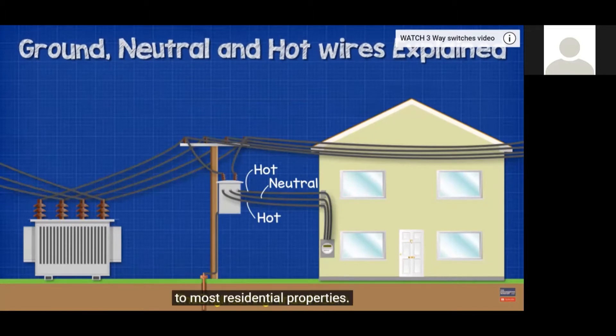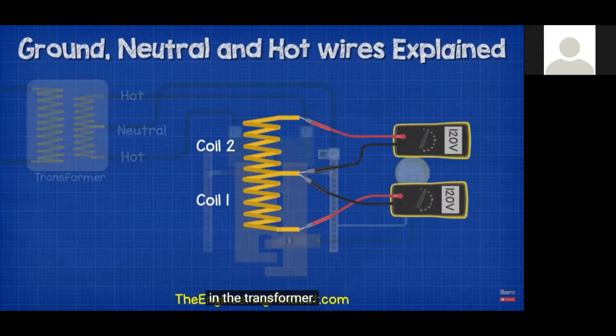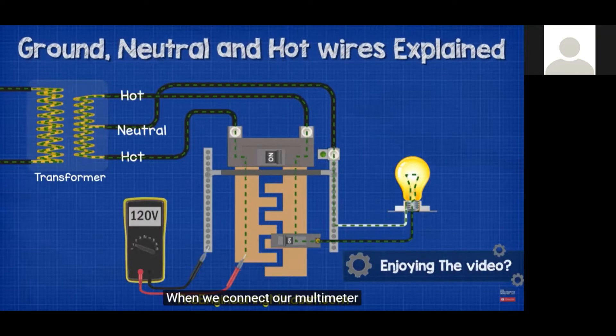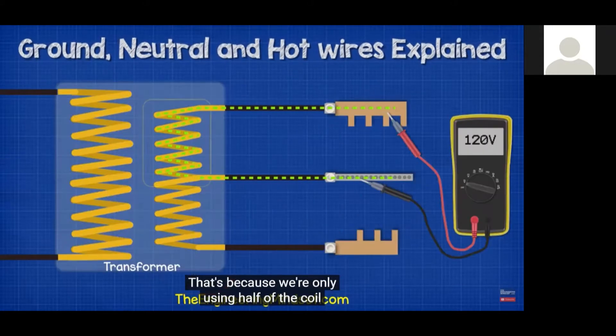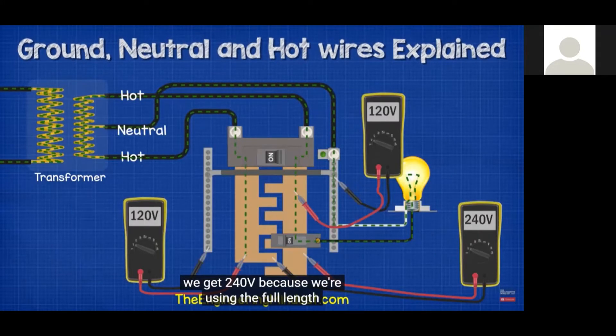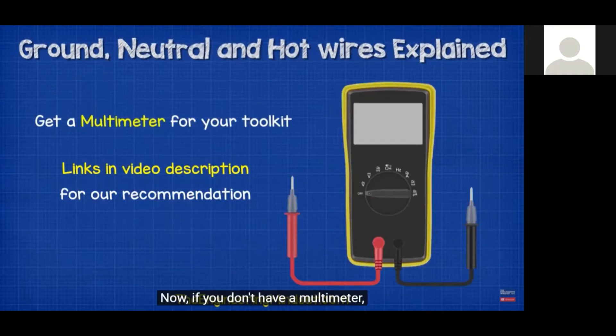In North America we have a split-phase supply to most residential properties — two hot wires and one neutral. We have 120-volt coils connected together in the transformer with the neutral connected to the center. Connecting a multimeter between a hot and the neutral gives about 120 volts; connecting between the two hots gives 240 volts because you're using the full transformer coil. If a load draws 20 amps, the hot carries 20 amps to the load and the neutral carries 20 amps back to the source. A current clamp meter can measure current in the cable.